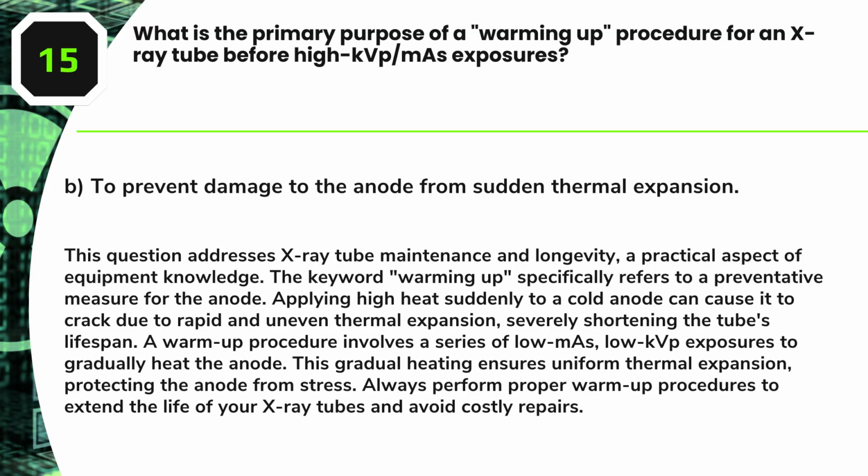Answer: B. To prevent damage to the anode from sudden thermal expansion. This question addresses X-ray tube maintenance and longevity, a practical aspect of equipment knowledge. The keyword warming up specifically refers to a preventative measure for the anode. Applying high heat suddenly to a cold anode can cause it to crack due to rapid and uneven thermal expansion, severely shortening the tube's lifespan.